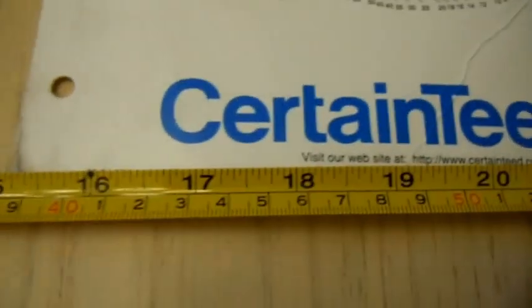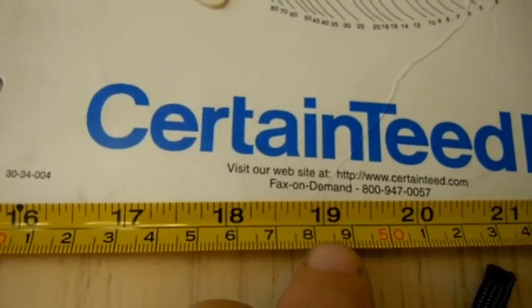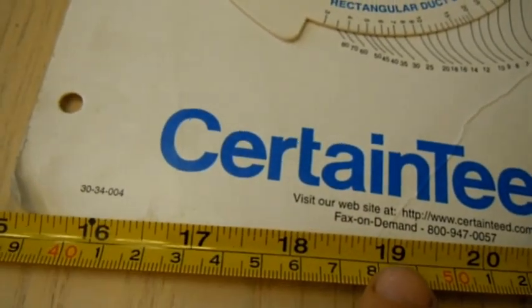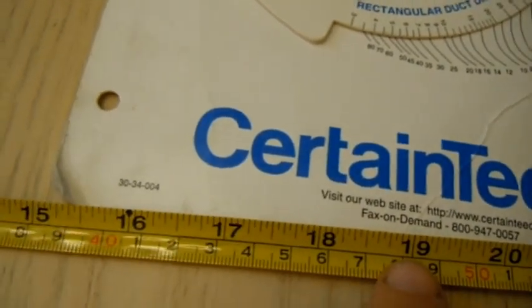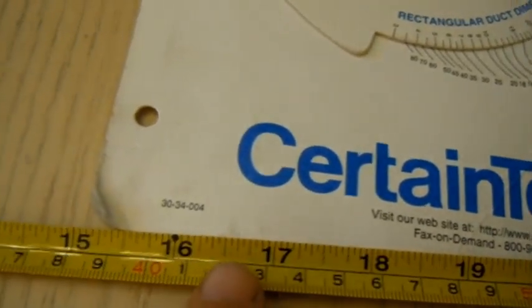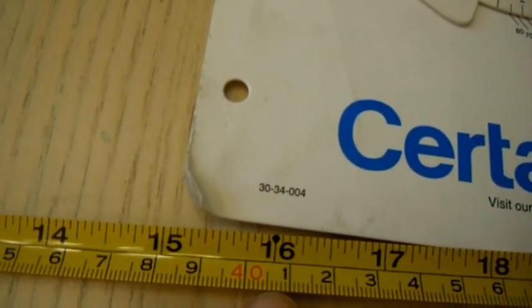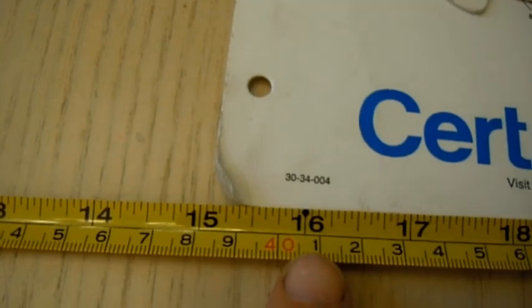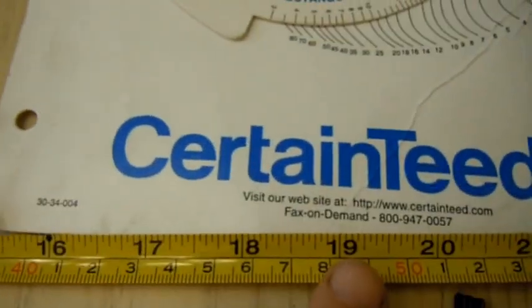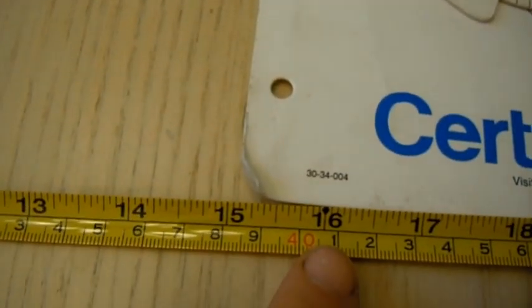So what we have is a 19 by 19 square duct. So that square duct, however, is an inch and a half thick. So what we're really going to do is we're going to subtract three inches from 19 and we're going to get 16. So what we really have for the inside diameter of that 19 by 19 duct is 16 by 16 on the inside.